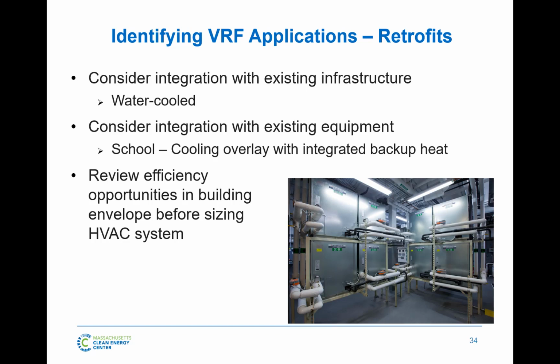On the retrofit side, then there's a few more things you can look at. We've really spent all this time describing air-cooled VRF. That's where you have a unit on the roof or outside that's pulling heat from the outside air or pulling heat from the building and rejecting it outdoors. Water-cooled VRF does exist. It is fairly common. Here's a picture of a bunch of water-cooled VRF units installed in a retrofit application.